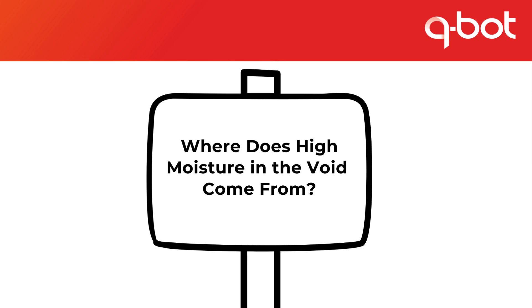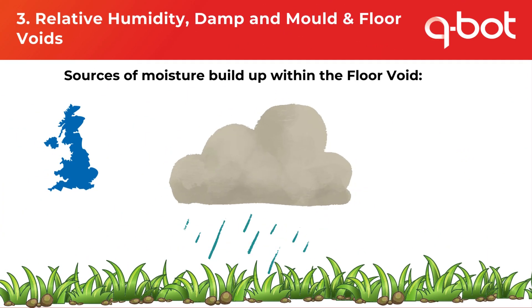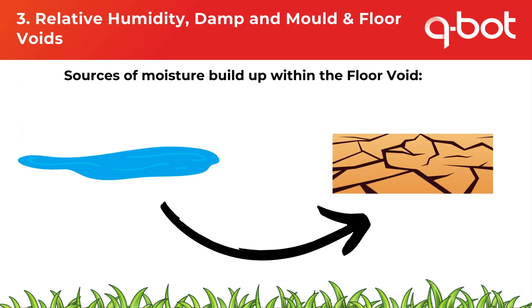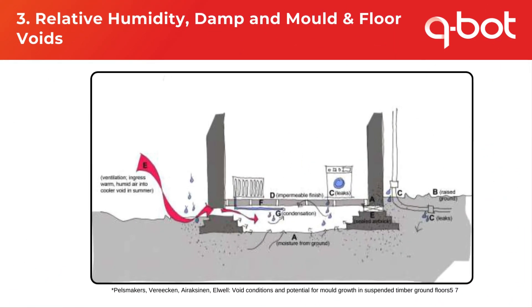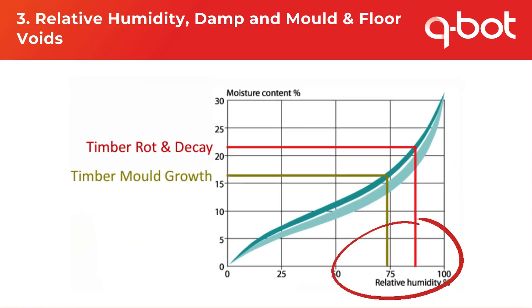Air infiltration from floor voids creates invisible health hazards as fungal spores, microbes and bacteria are transferred into our living space. But where does the moisture in the void come from? Predominantly it comes from the ground — our climate means the ground is mostly wet, and moisture moves from wetter to drier areas naturally due to hygroscopic movement. Floor voids are much drier than outside because they're shielded and heated by the property, creating a constant suction of moisture into this underground void. Other sources include lack of external site drainage, leaks from services, external air ingress especially in summer, and undetected roof leaks. All of these contribute to the 60–95% relative humidity found within floor voids and the resultant damp, mould and decay. This range lies within the sweet spot for timber mould growth, rot and decay — well outside recommended safe humidity levels.